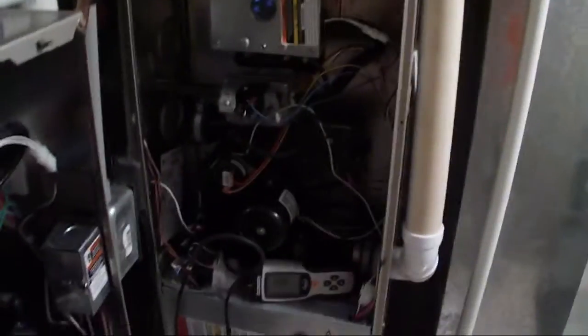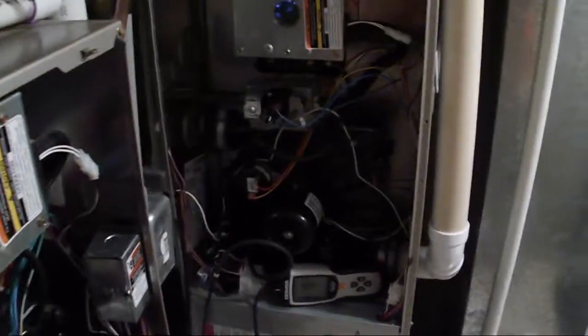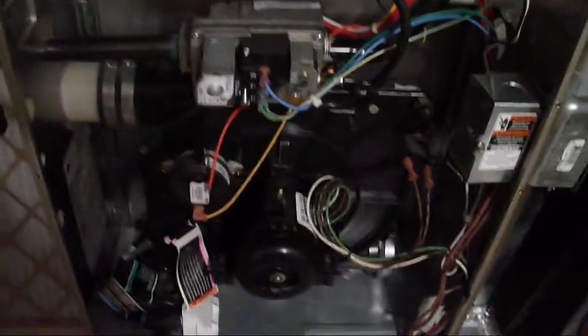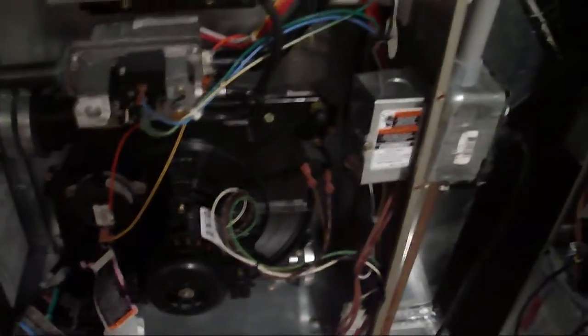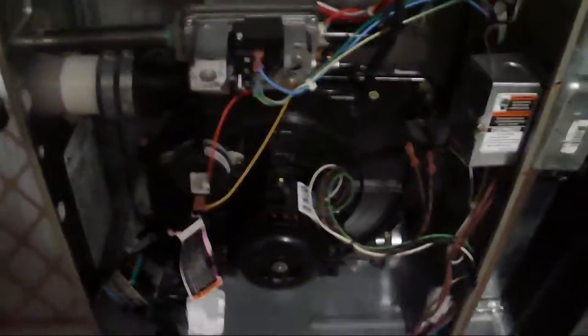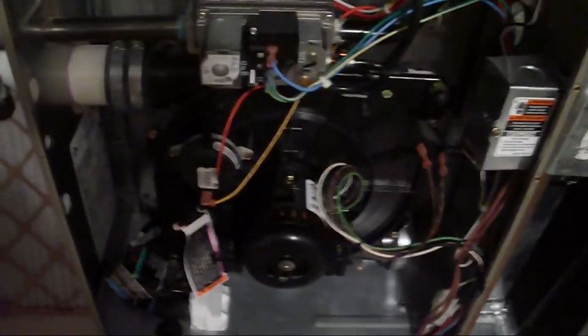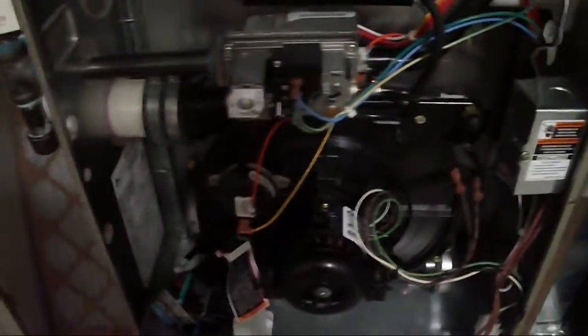The mechanic is checking the temperature of the air coming out of the register and also checking for carbon monoxide levels. The upstairs furnace was completely safe. No carbon monoxide. It was blowing 108 degrees at the vent in my bathroom. This is the first floor furnace that's running right now.